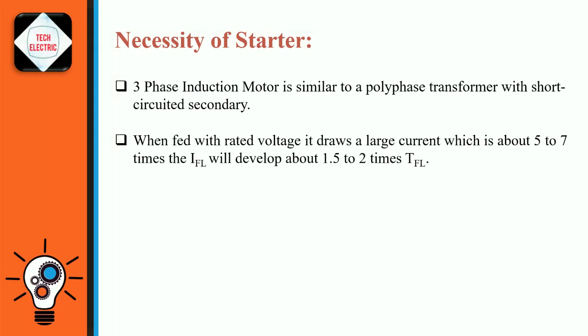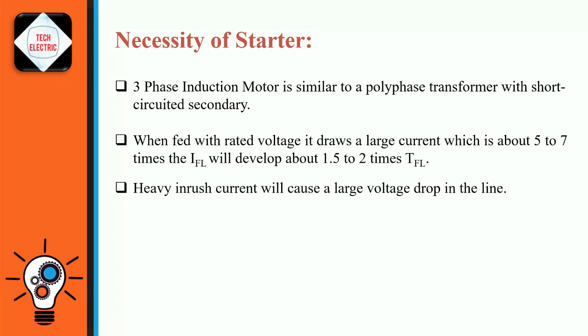This heavy inrush current of short duration may not cause harm to the motor since construction of the induction motor is rugged. Also, time duration of this heavy current is not that long as to cause excessive temperature rise which may damage the insulation of windings. But this heavy inrush current will cause a large voltage drop in the line to which the motor is connected. So, other equipment connected to the line may receive a reduced voltage that affects their working. To mitigate these issues, Auto Transformer Starter is employed.